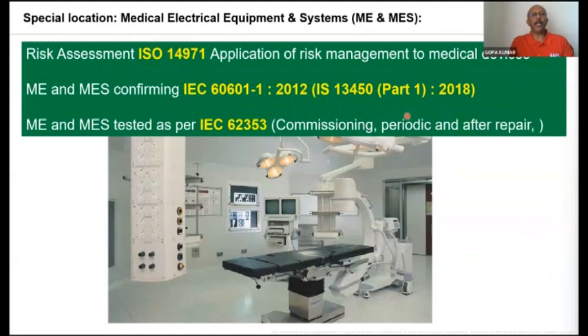this particular standard. Number 3, when you buy a medical electrical equipment or a medical electrical system, and if you install it in your operation theater, after the installation or during commissioning, during periodic test, and after any repair, you are supposed to do a test as per IEC 62353. These 3 things are actually mandatory in a medical location.